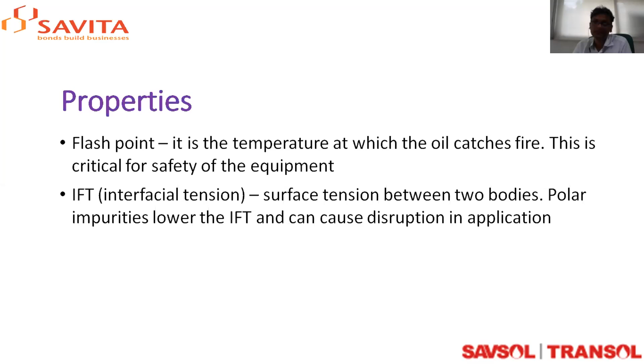Apart from this, there is another parameter people generally use called IFT, interfacial tension. Basically, interfacial tension is a surface tension between two different bodies, say water and oil. I won't go deep into chemical terms, but one has to understand what it indicates. If your IFT is low, it is an indication that there are polar impurities present in the oil. If your IFT is high, then the oil has very low polar impurities. These polar impurities are important because they drastically hamper the electrical properties of the transformer. That's why one has to always keep an eye on the IFT of the oil.